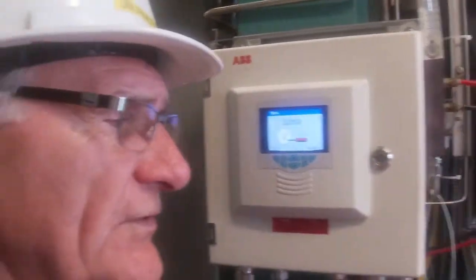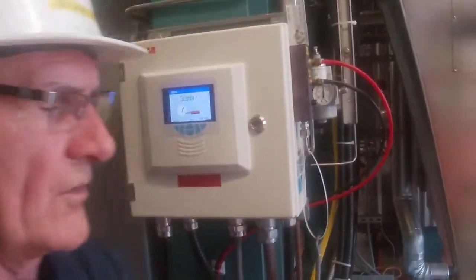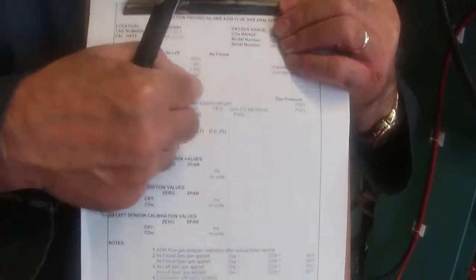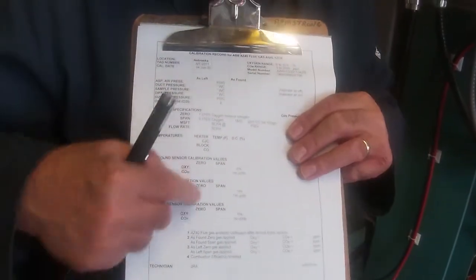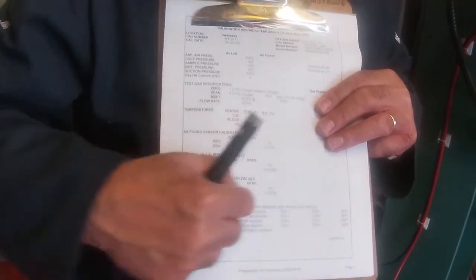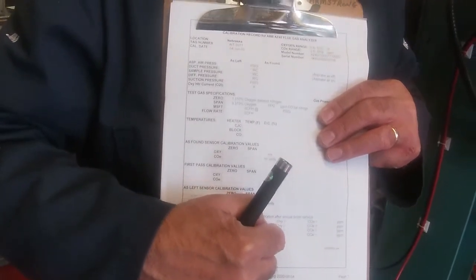So to do this calibration, we made up a spreadsheet. And out of this spreadsheet, we're going to fill all this data in. Not everything is on the electronics. Some of it, we're going to take some draft pressures inside the actual machine itself to see whether it's plugged up or not. Down at the very bottom, I've got the as-found values, which we're going to do early in the game, and then the as-left values when we've finished the calibration. There's quite a bit of information to fill in down this sheet, which we're going to get from the machine itself.